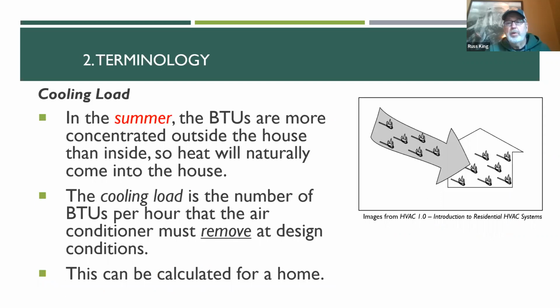So cooling load, that's an important number. You'll hear me say loads, heating loads, cooling loads, load calculations, things like that. Well, the load is how many BTUs are coming into the house. In the summer, BTUs are more concentrated outside, and so they're naturally going to want to come into the house, okay? So a cooling load is how many BTUs per hour are coming in that have to be removed. And it's something that can actually be calculated on a house by looking at the windows and the walls and the floors and how much insulation there is and what direction the windows are facing and things like that. So it's a number that you can calculate, to determine what the load is on a house in the summertime, and we call that cooling load.